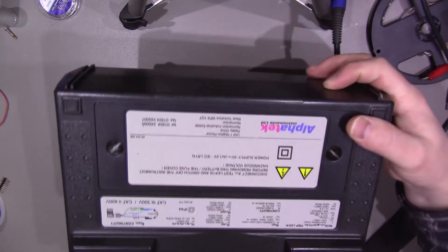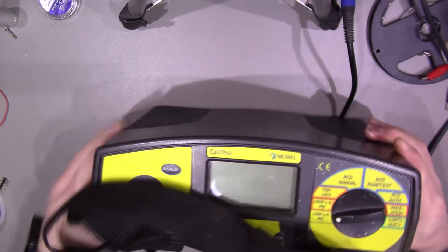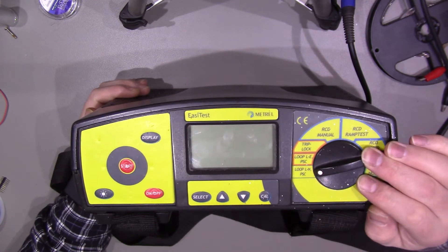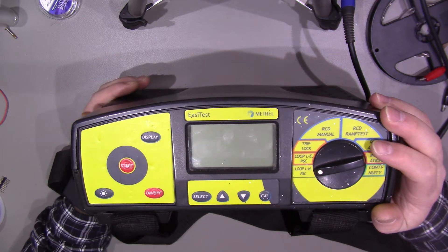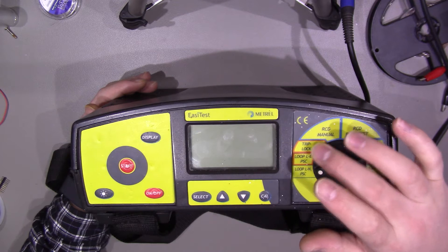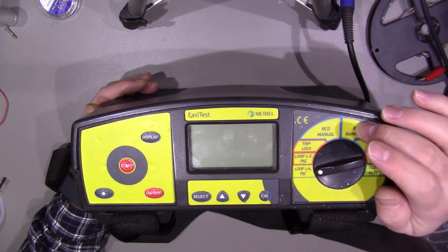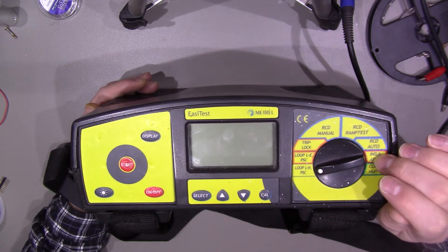That's pretty much all there is to the unit itself. You've got the battery pack — it takes four C-cell batteries giving a total of six volts. Although this tester predates the 17th edition wiring regulations (which came in 2008), it does all the standard tests I need. We've got loop tests for live/neutral and line/earth, trip-lock test for use with RCDs, RCD manual, RCD ramp test, RCD auto, insulation testing, and continuity testing. The main one I wanted was insulation testing.